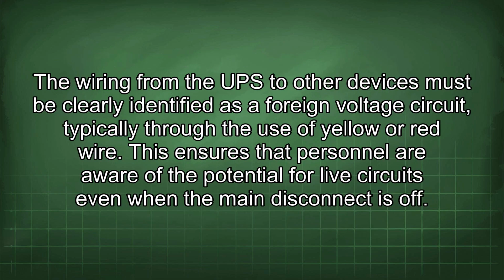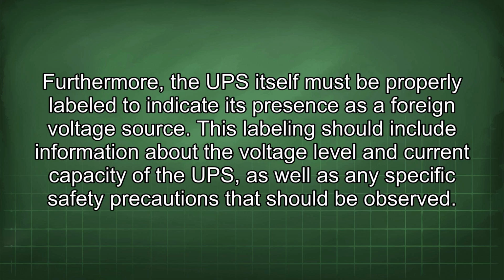The wiring from the UPS to other devices must be clearly identified as a foreign voltage circuit, typically through the use of yellow or red wire. This ensures that personnel are aware of the potential for live circuits even when the main disconnect is off. Furthermore, the UPS itself must be properly labeled to indicate its presence as a foreign voltage source. This labeling should include information about the voltage level and current capacity of the UPS, as well as any specific safety precautions that should be observed.